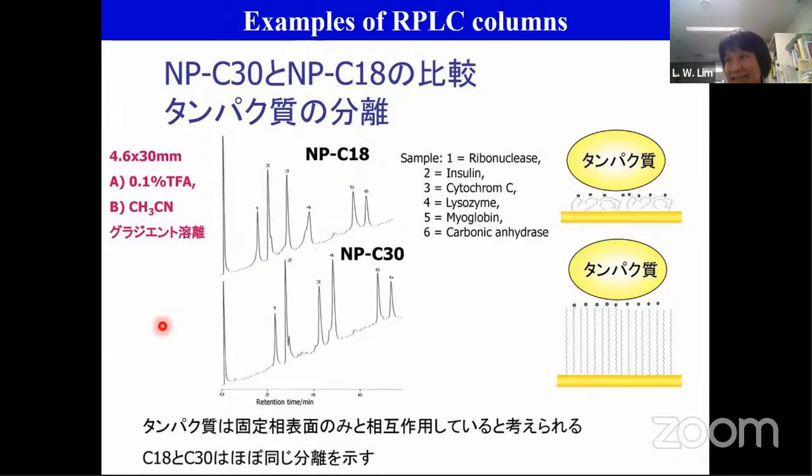Yes, tailing. We also have fronting. Tailing is maybe like this. Fronting is before the peak, tailing is after the peak. This usually has to do with your column. If your column is sometimes contaminated, you can solve the tailing by washing the column with a different eluent.